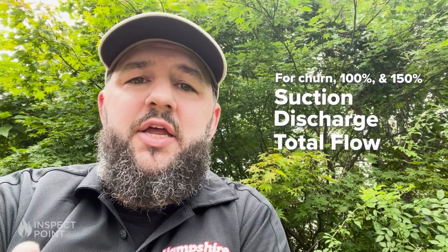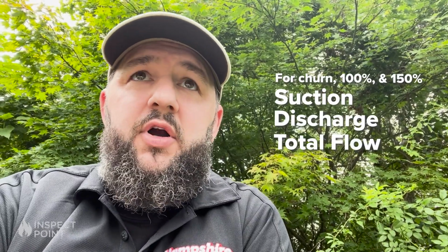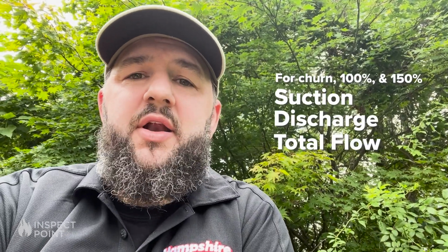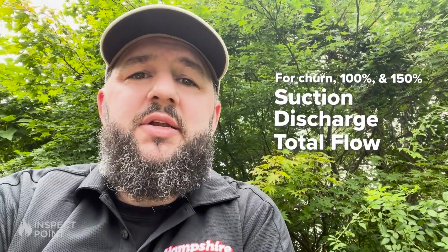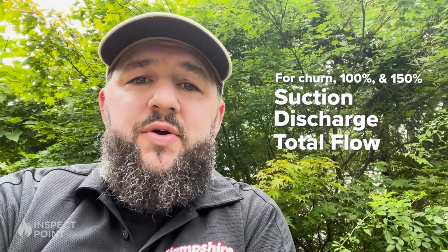The only data points you need to get your current performance curve are your suction, discharge, and total flow for churn, 100% and 150%. Suction, discharge, and total flow.